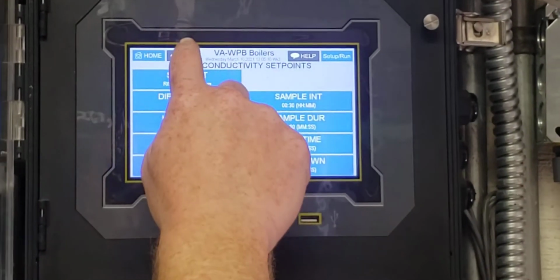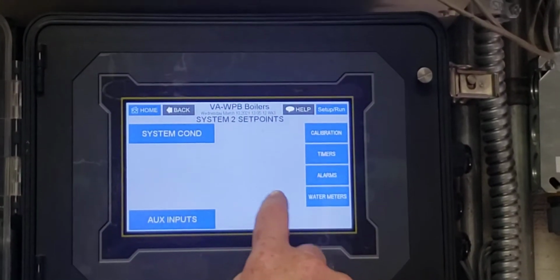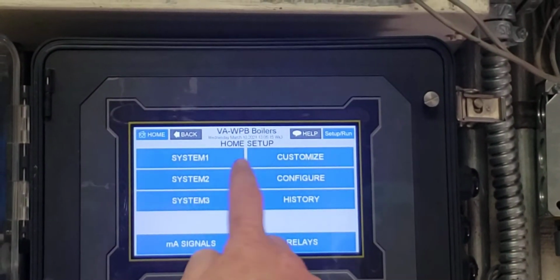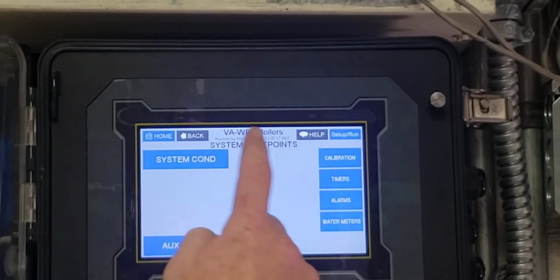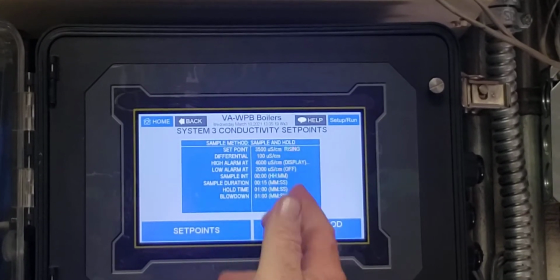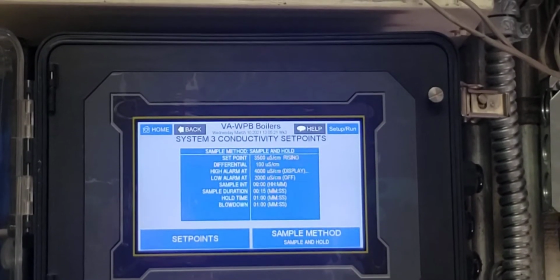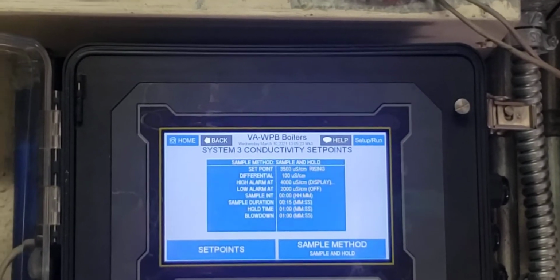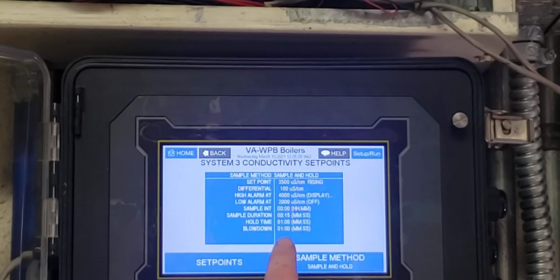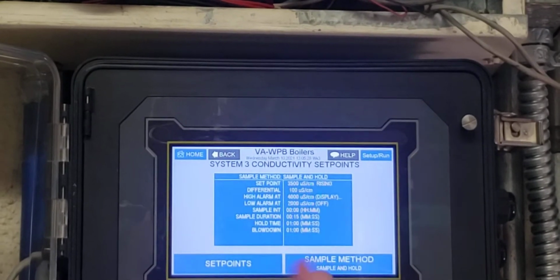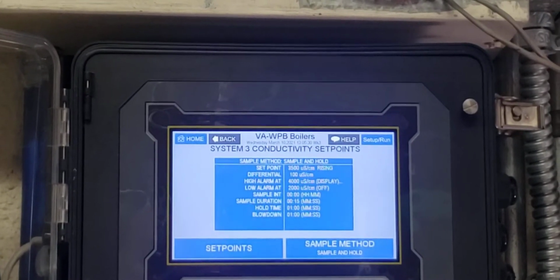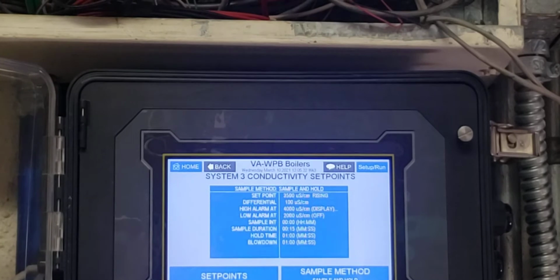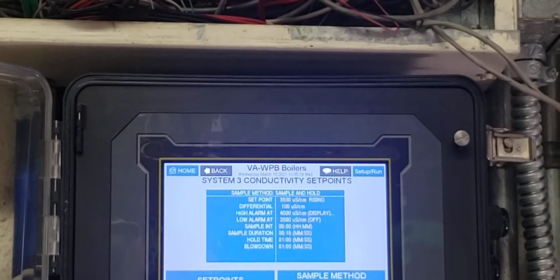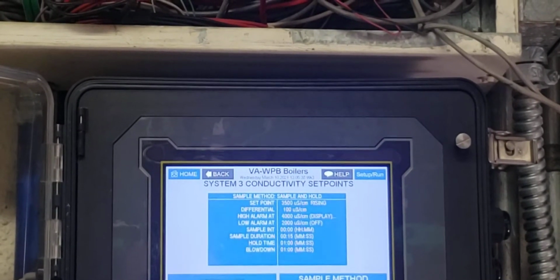Now you can look at that duration on that time. This is boiler 3. I think the boiler is offline, and this is all the defaults in here for this one. Yeah, this is a 3500 one. So yours was sample for 15. Well, that one's sample for 15. This was just whatever was defaulted in the controller. Oh, okay, it has no sample interval. So this one was never set up. Yeah, so the other one, you have it set.